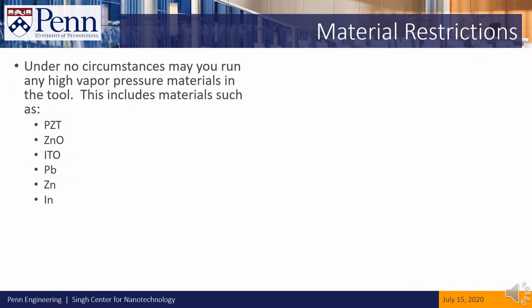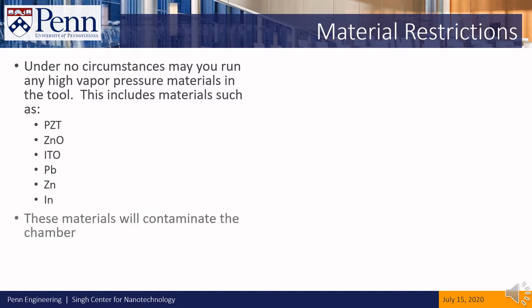You may not, under any circumstances, process any samples with high vapor pressure materials. Some examples of these materials are listed here. If your sample has any of these materials on it, it will contaminate the chamber, and if that happens, the tool will have to be taken down for cleaning, which puts it down for everyone, including you.